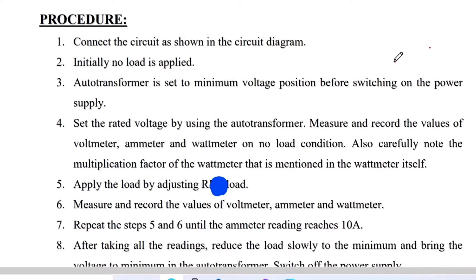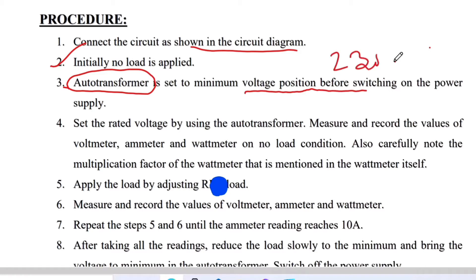Going through the procedure: connections are made as per the circuit diagram. Initially, no load condition is applied — none of the load is applied. We are using a special arrangement of an auto transformer to give voltage gradually from minimum to maximum 230 volt. By using the auto transformer, 230 volt is set up, then measure and record the values of voltmeter, ammeter, and wattmeter under no load condition.